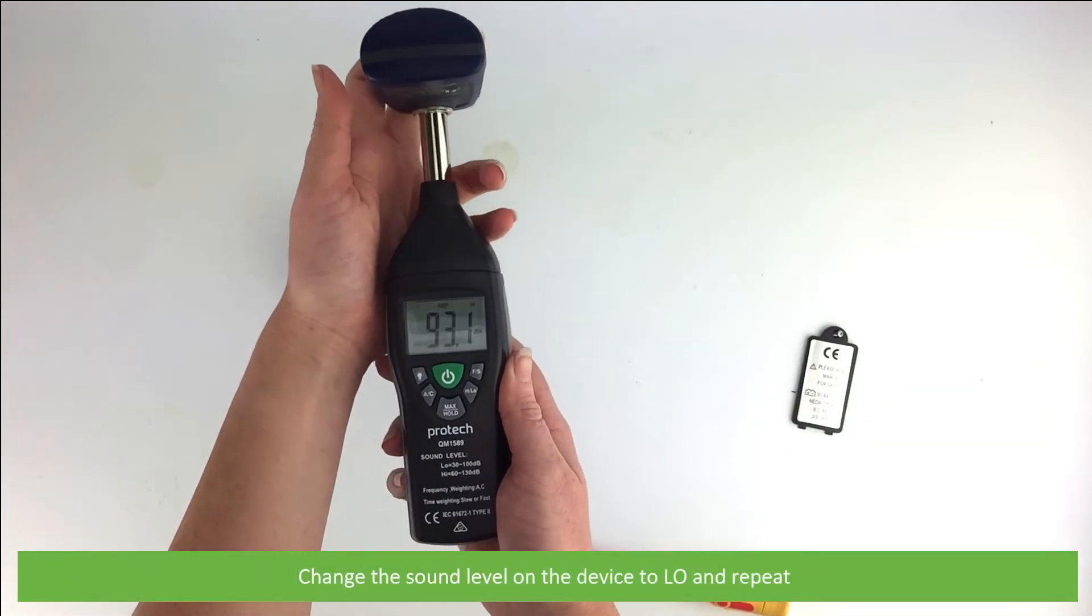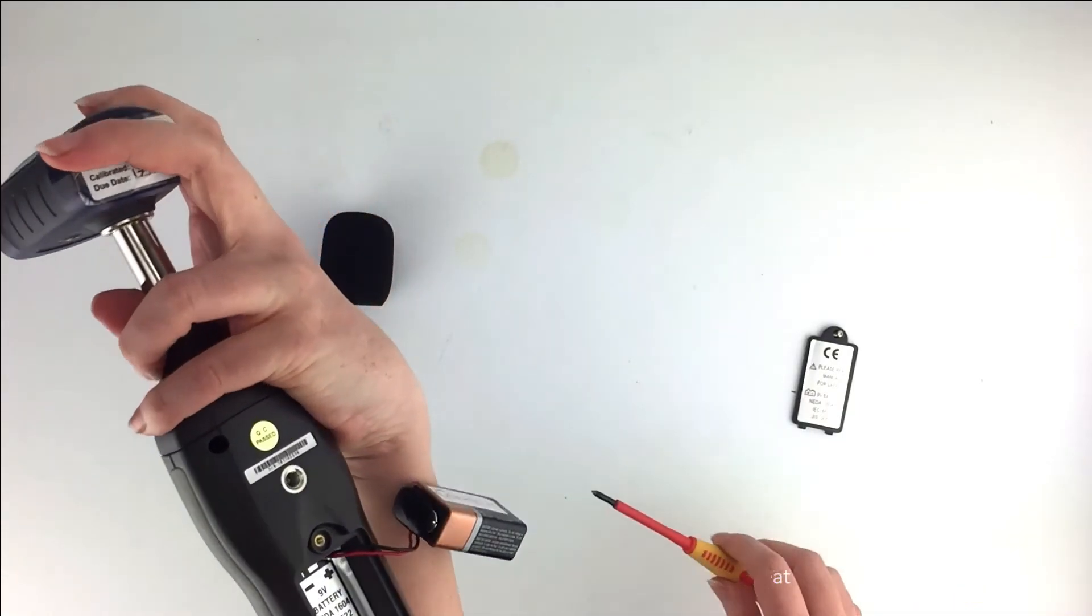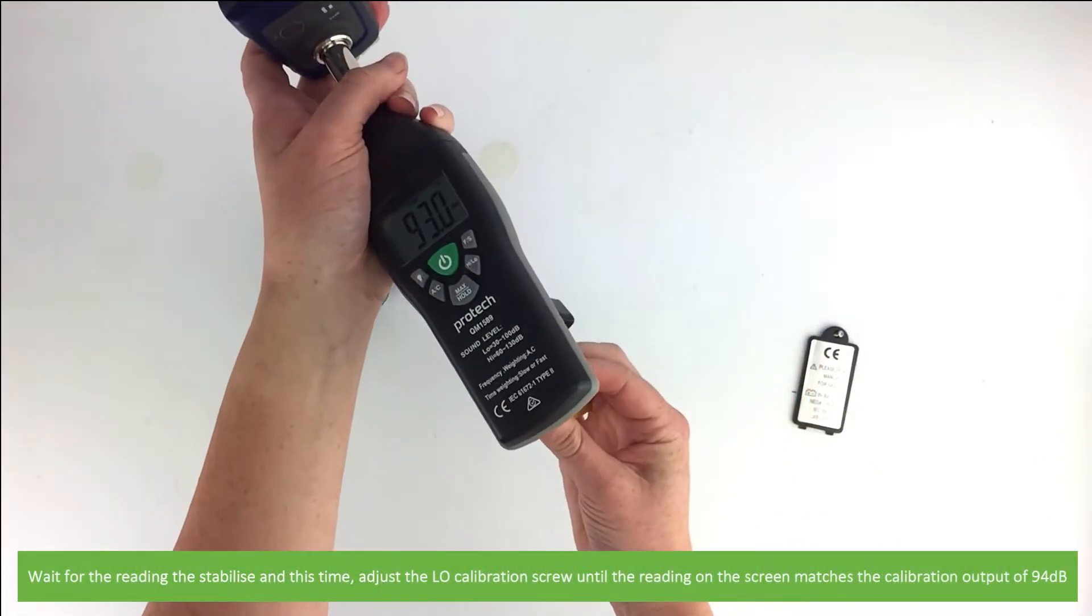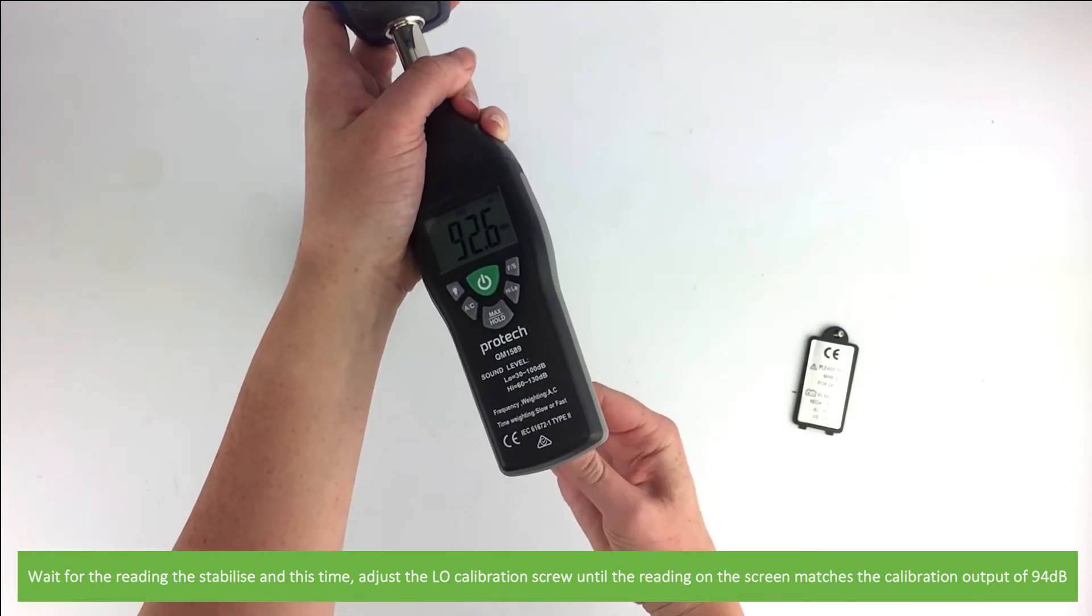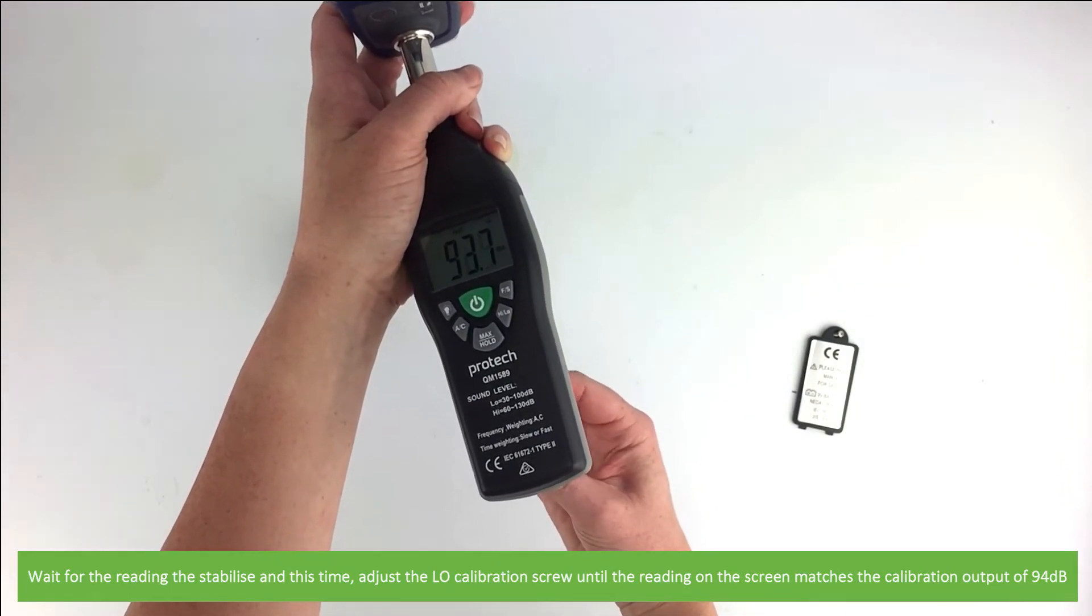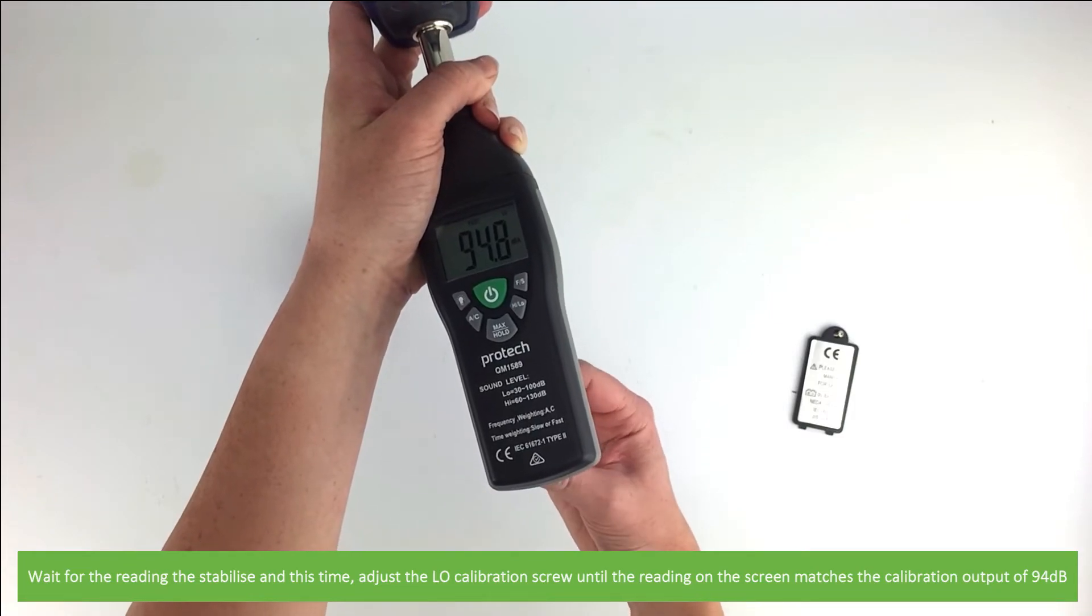All there is to do is reset the low calibration. Change the sound level to low on the meter and repeat. Wait for the reading to stabilize. And this time adjust the low calibration screw until the reading on the screen matches the calibration output of 94 decibels.